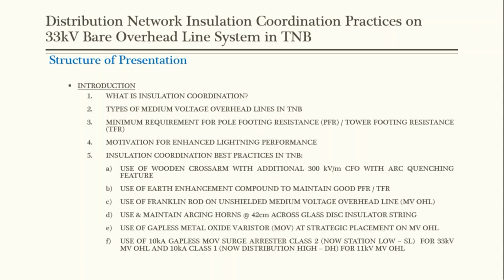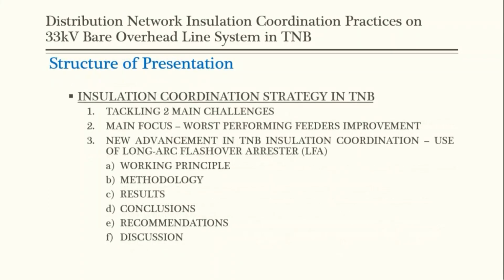After that, I'll be talking on the insulation coordination best practices currently in TNB. And moving on, I'll be talking on the insulation coordination strategy in TNB using new technology, because we have to tackle two main challenges. And our main focus will be to improve on the worst performing feeders. I'll be talking on the new advancement in TNB insulation coordination with the use of long arc flashover arrestor, which is a new technology in insulation coordination for distribution network in TNB.